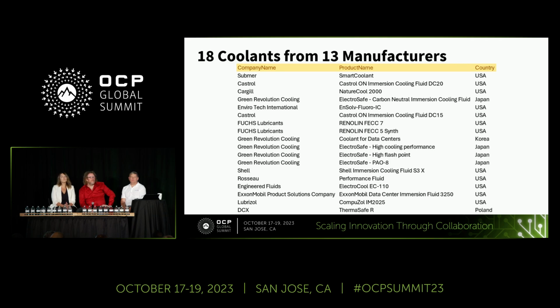Yeah, thank you, Gustavo. But I'm talking about system level. We have the immersion and the baseboard and all the components. So if we put it in a tank, seal it, increase the pressure, or we test it with a similar fluid at high pressure. We test components, so we are going. The OCP has some recommended guidelines for testing materials by Soxhlet extraction. But the tests are usually done during 48 hours at atmospheric pressure at 50 degrees C.